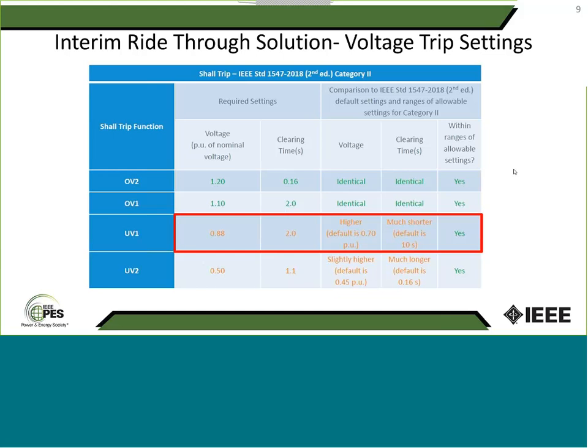ride-through requirements in Massachusetts are only for solar generation for now, and may be extended to storage in the near future because we are seeing higher penetration of storage as well. But they're not applicable to rotating machines because the penetration of rotating machines is low in the state. So with that clarification, if you look at these settings, the only change compared to the old 1547 is the under-voltage 2, which is 50%.